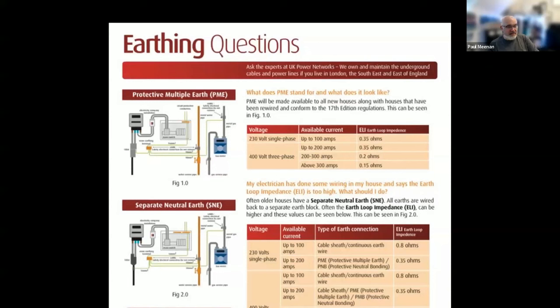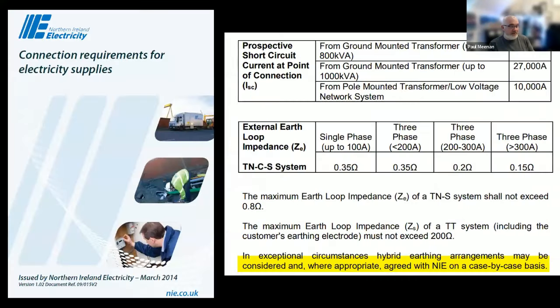We have what we call PME, Protective Multiple Earth, also known as TN-C-S. And a separate neutral and earth, also known as TN-S. And the networks originally were TN-S. They're now pretty much all combined neutral and earth, unless they're on a private transformer. Personally, I think separate neutral and earth was always the way to go. But just to let you know, some DNO companies will allow a hybrid. So the photo you'll see in a minute is a hybrid of multiple earthing systems. It can be confusing for an electrician when they're trying to ascertain what it is.